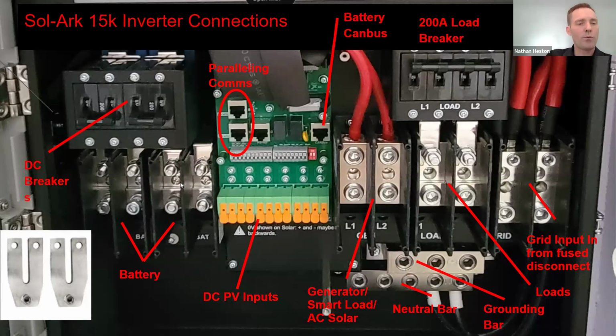So you'll notice that there are 4 connections there. You can also buy these combiner bars if you want to have a single home run to the inverter with a 4-aught connection and combine these two, utilizing just a single battery connection. In the center of your screen, you have the DC inputs coming from your solar. You have 3 independent MPPTs, and there are 2 parallel connections for each MPPT. So having a total of 6 connections there, plus and minus for 6.